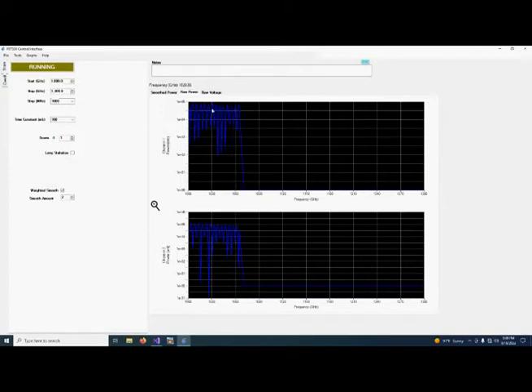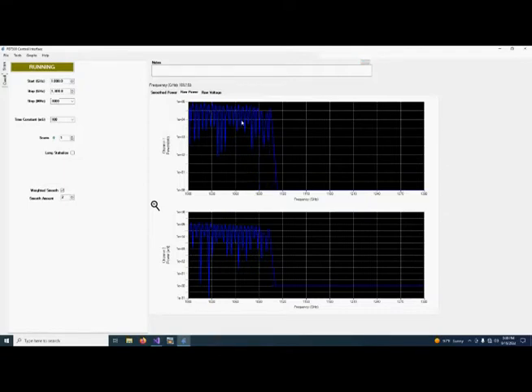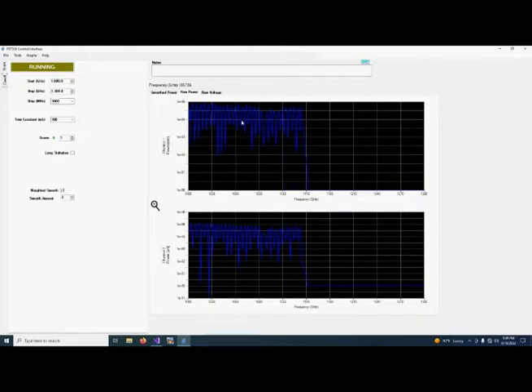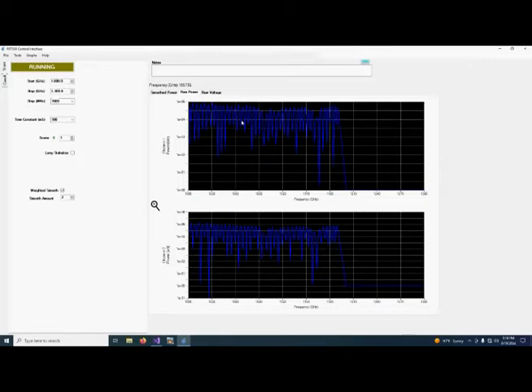If you're looking at narrow transitions in gases and that transition should fall on one of these nulls where because of the coherent detection, the terahertz radiation in the local oscillator and the terahertz radiation through your sample destructively interfere, then you're not going to be able to measure the line. You're just out of luck.